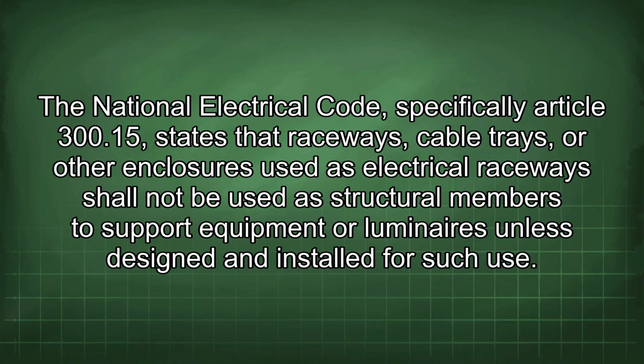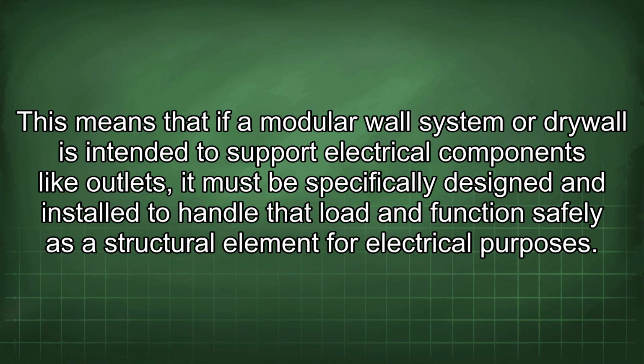The National Electrical Code, specifically Article 300.15, states that raceways, cable trays, or other enclosures used as electrical raceways shall not be used as structural members to support equipment or luminaires unless designed and installed for such use. This means that if a modular wall system or drywall is intended to support electrical components like outlets, it must be specifically designed and installed to handle that load and function safely as a structural element for electrical purposes.